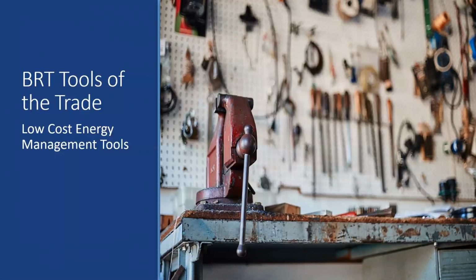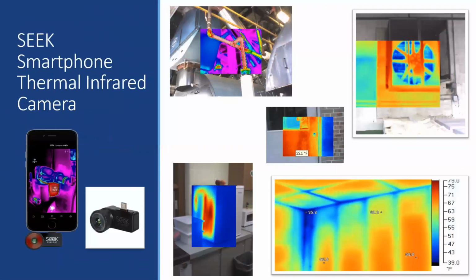They're very handy. First, we have the Seek infrared thermal camera. You can find problems like air leaks, missing insulation, or even electrical overloads in your power lines. It is tiny, it is portable, and it can be used with several smartphones. And what's really nice about the camera is it will give you a scale of what you're currently seeing, and it will give you multiple set points so that you can measure and compare your space.